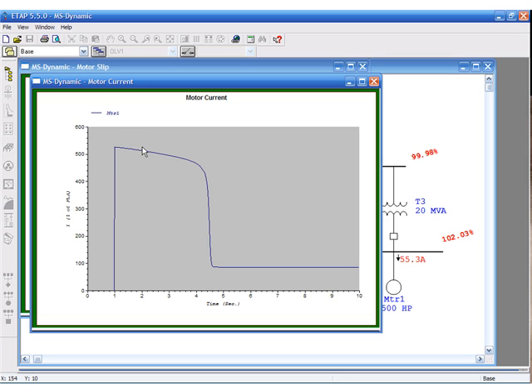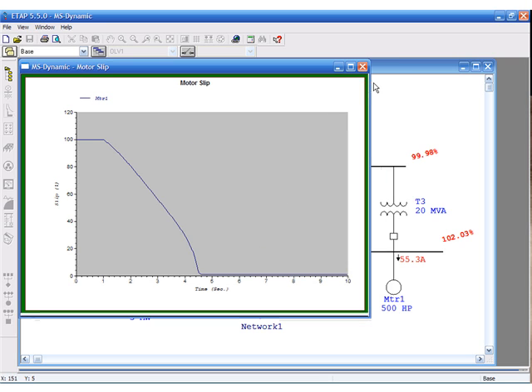As you can see, the curve is a smooth shape, indicating the circuit model was used for this calculation. And the motor slip. The motor started accelerating at t equals 1 and reached rated slip at around 4.5 seconds, giving us an acceleration time of 3.5 seconds.